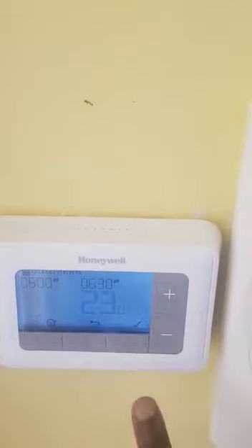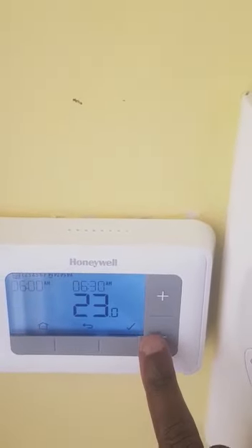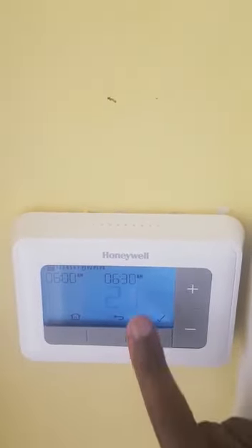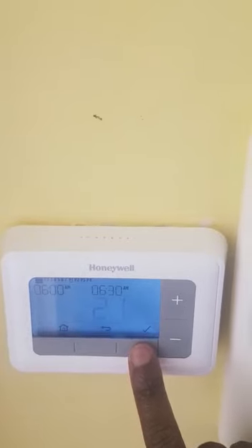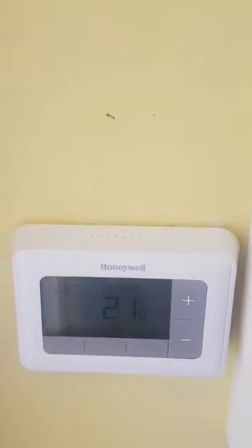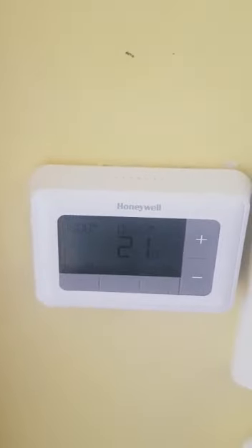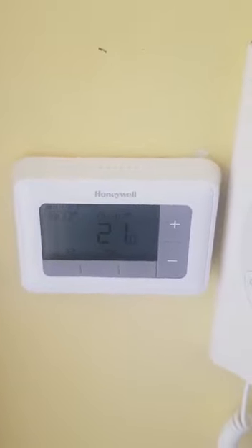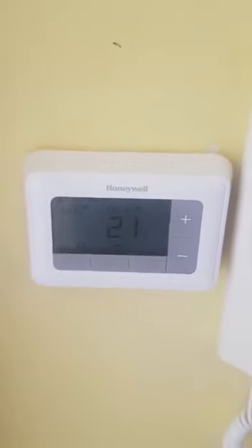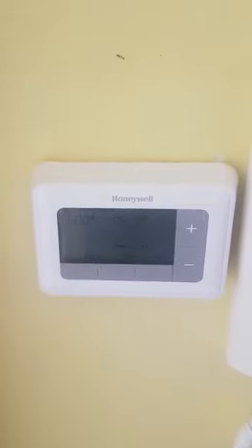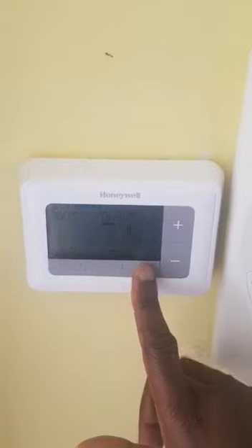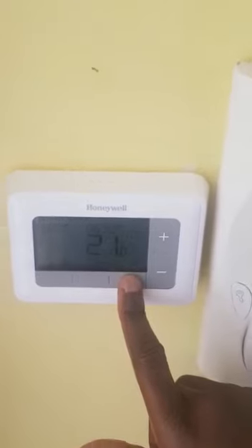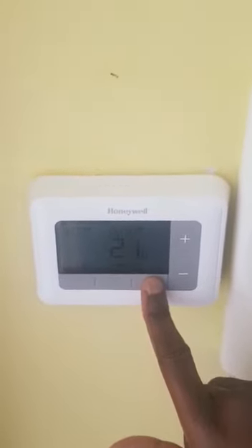Now finally we set the temperature, and we use the plus or minus button to set the temperature. You said you want to set it to 21. So I'm just going to come down to 21, and 21 is flashing. In order to set it, I will press the tick. Now important to remember, if the room temperature doesn't go below 21, it will not come on. If the room temperature is at 25, it will not come on. It's only if the temperature of the room is below what you've set it to, then the boiler will come on. I think in the winter time in here, the lowest would probably be 18, 17 or 18. Maybe 16 at a push.